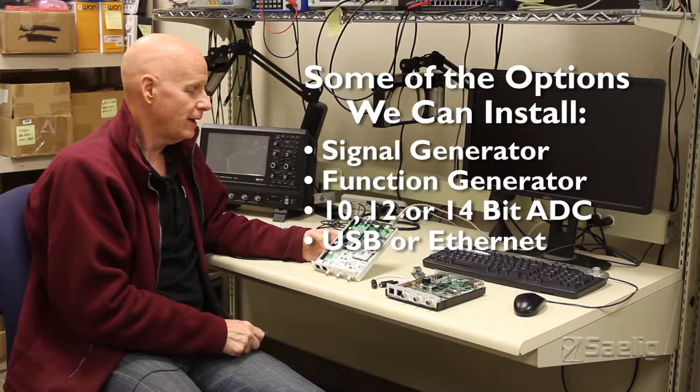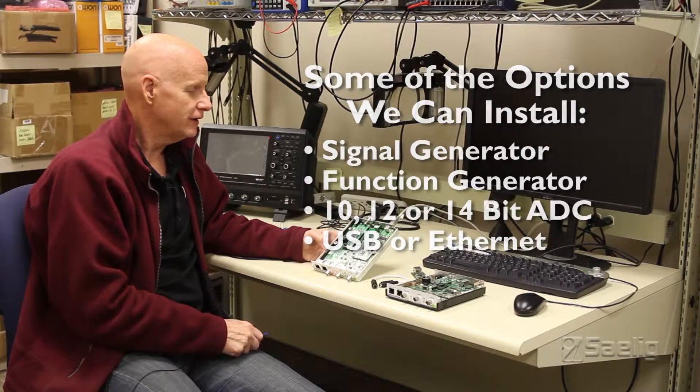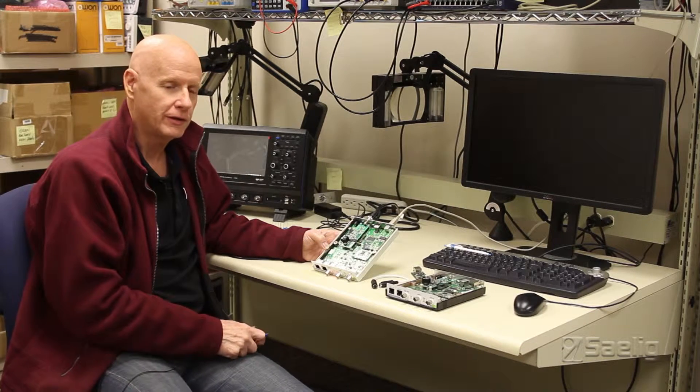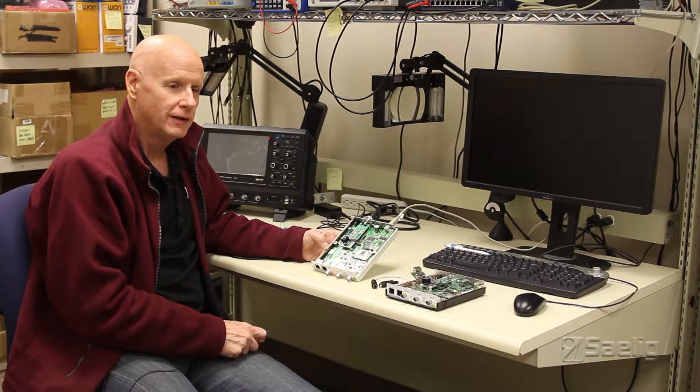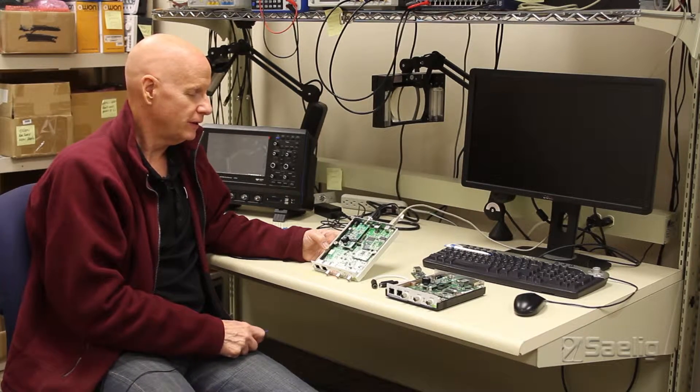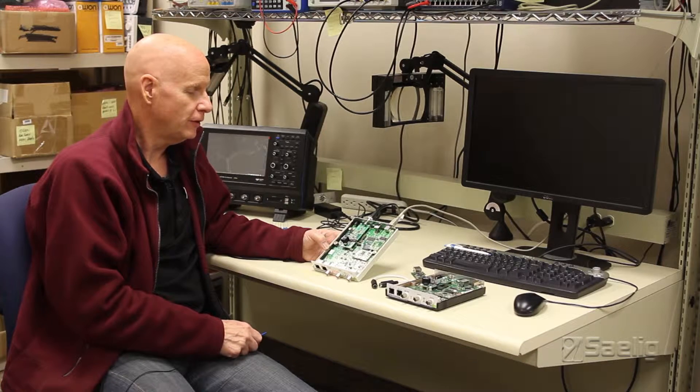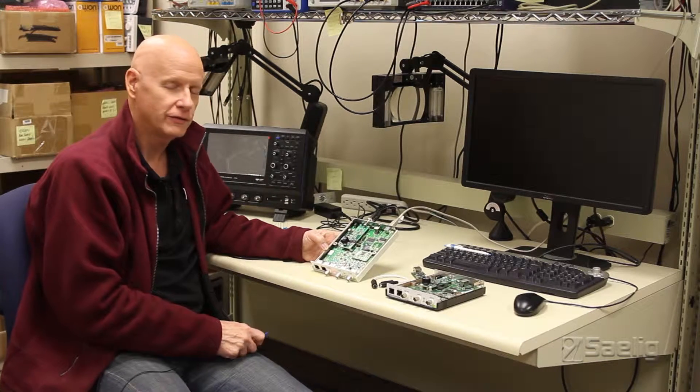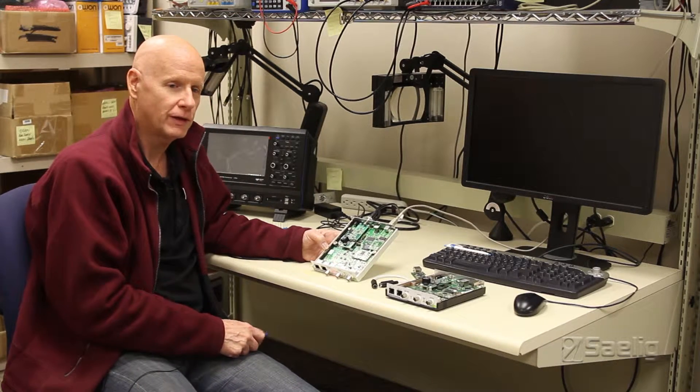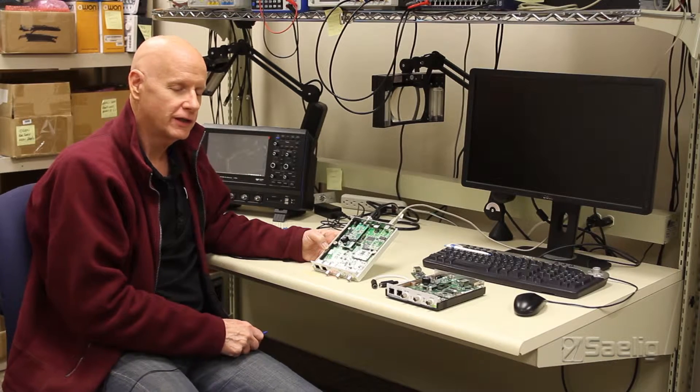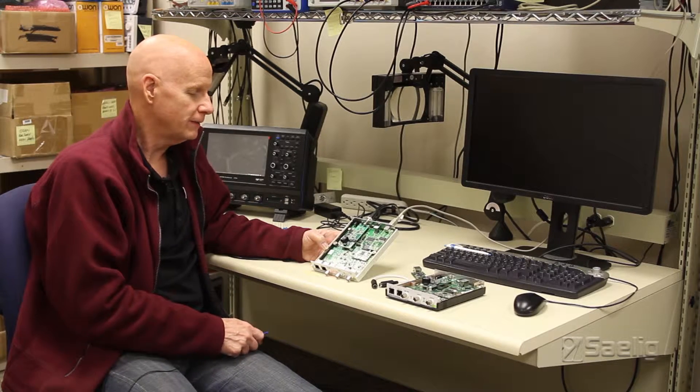These things are all installable here. What we do is we build up your CleverScope, we test it, we run it through the various calibrations as required, and we make sure the thing is working properly before we ship it out the door to you.